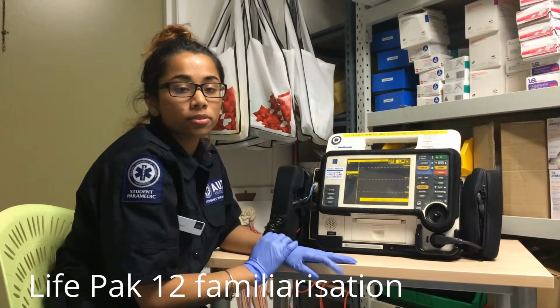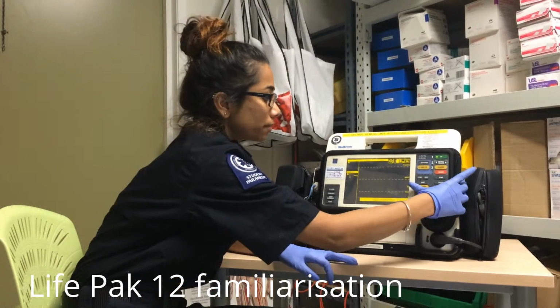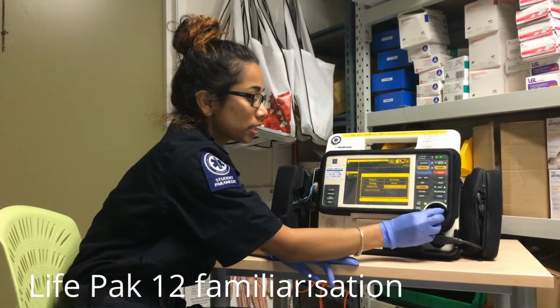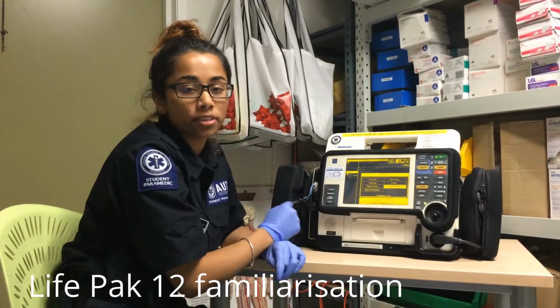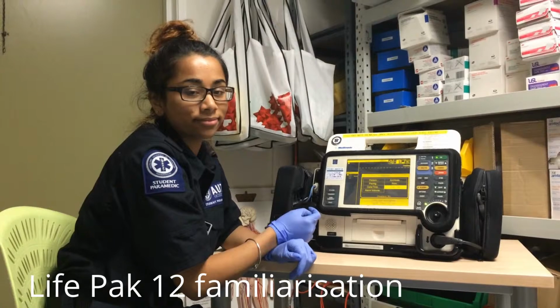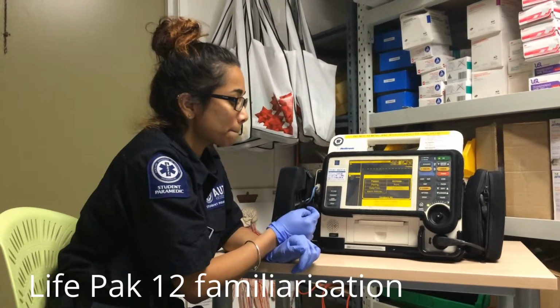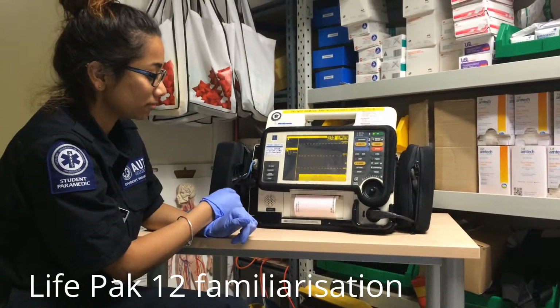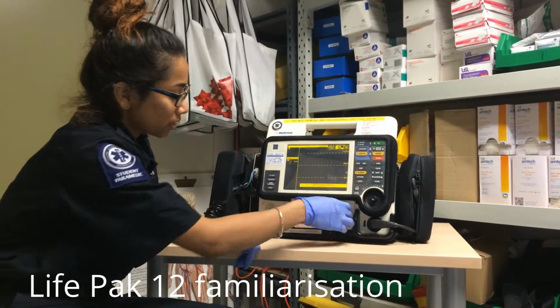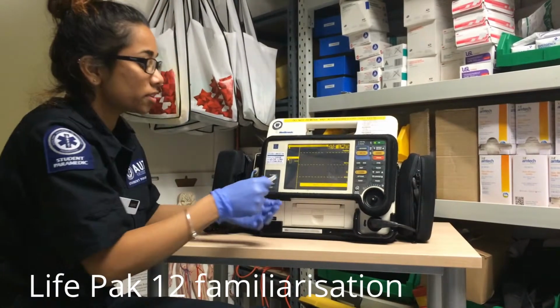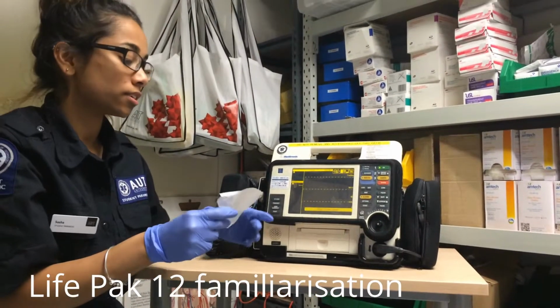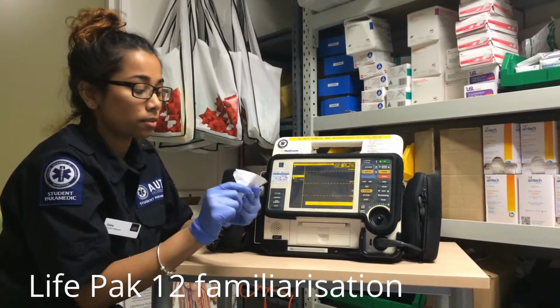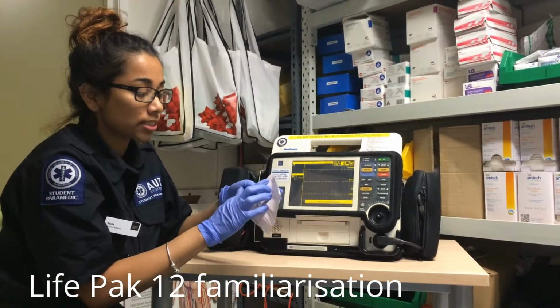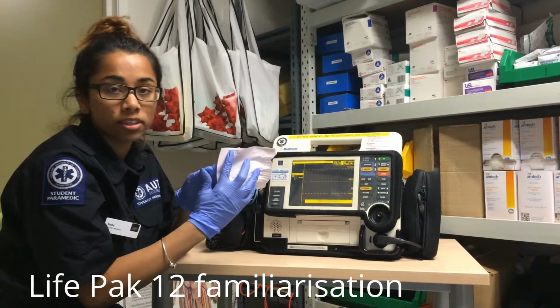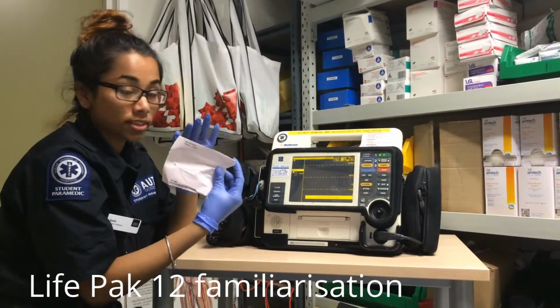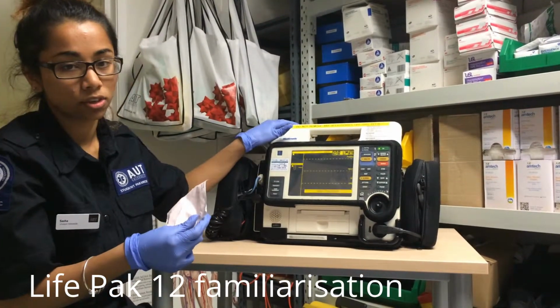So to do an operational test, you want to click Options, scroll down to User Test, and it will print out a user test for you. So when you click the user test, it will print out this user test for you, and it will say the date and the time, and it will also say user test pass. So it does say user test pass, so the machine is good to use.